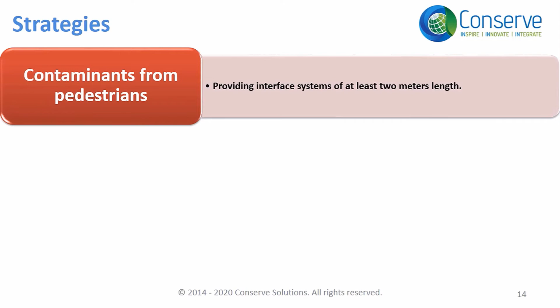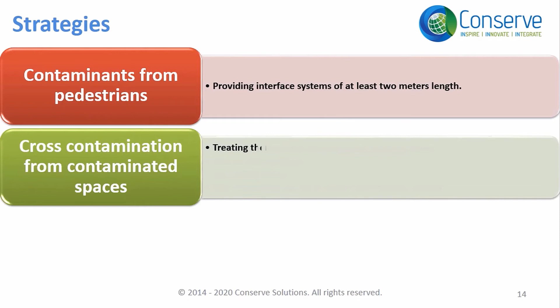Cross contamination from potentially contaminated rooms like copier rooms, printer rooms can be addressed by treating them similar to designated smoking rooms, which includes maintaining a negative pressure in the contaminated areas. Having a deck-to-deck partition, that is slab-to-slab partition instead of partition only up to the false ceiling. Self-closing doors and not recirculate the air in the air conditioning system that should be exhausted directly outside.